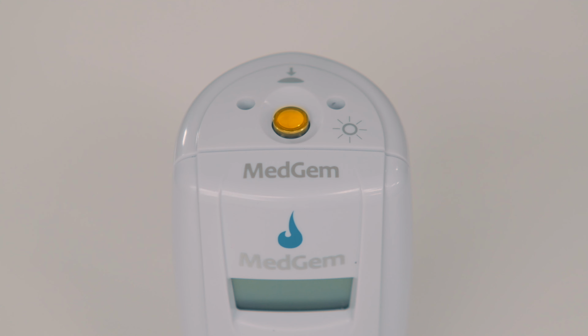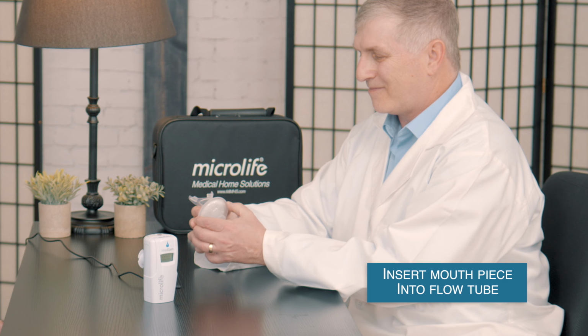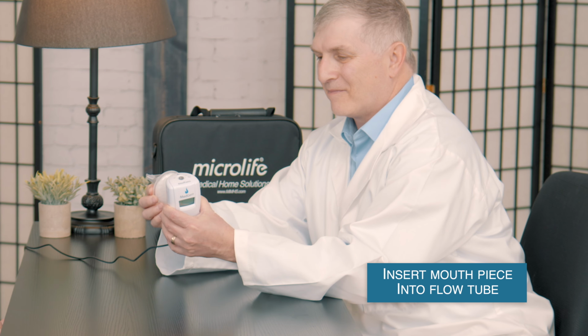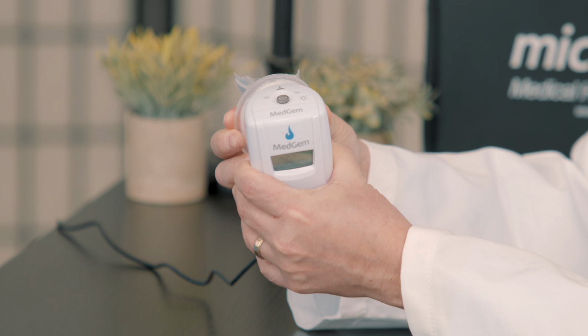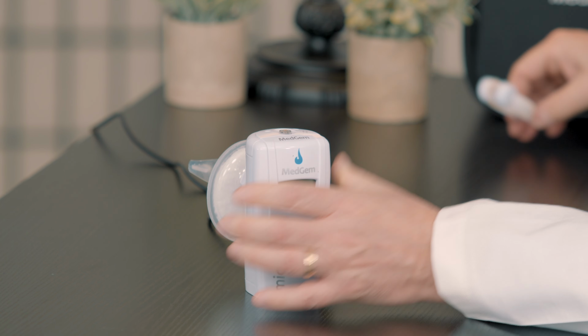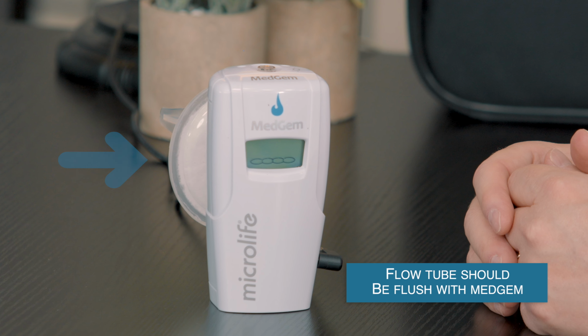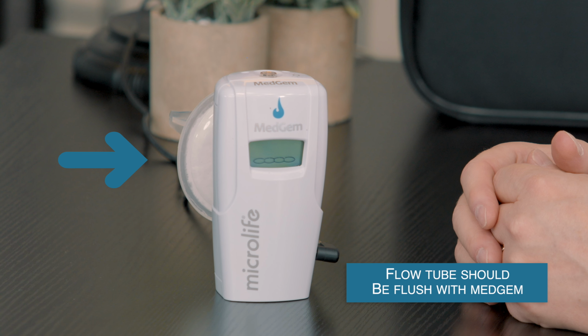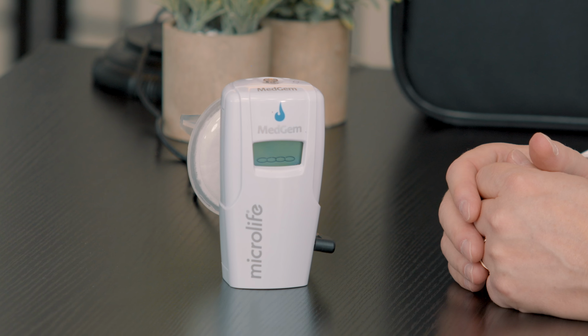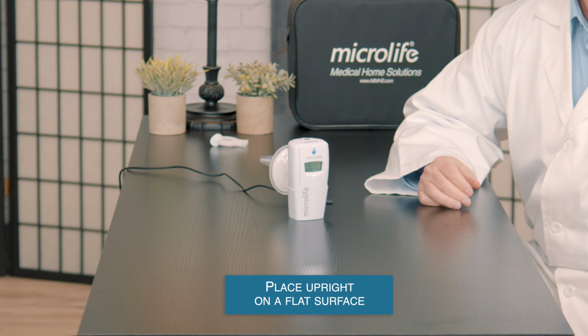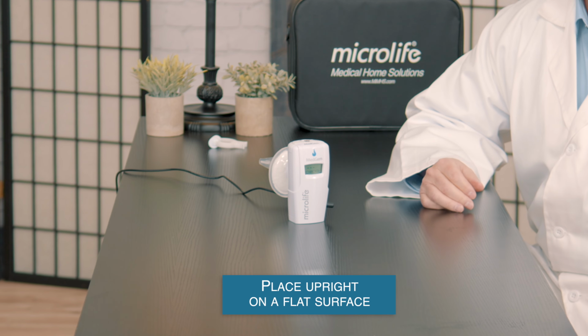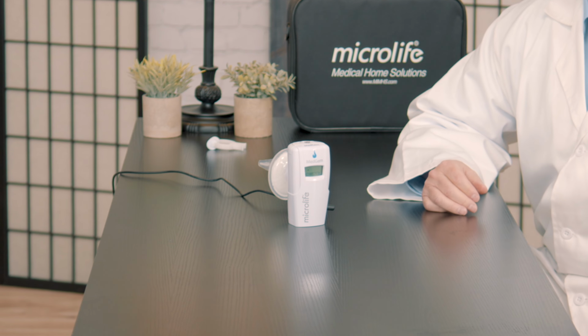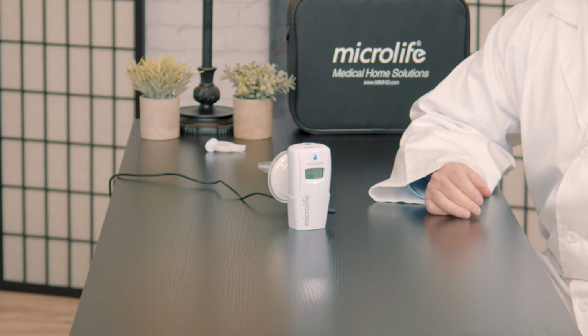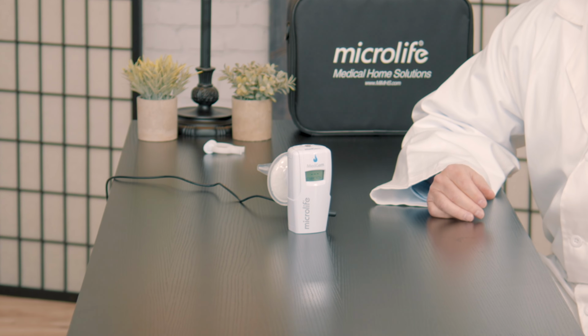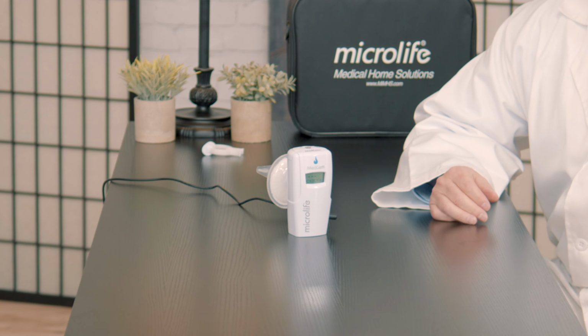Insert the single-use mouthpiece into the flow tube on the back of the device. Ensure they fit snugly to prevent any air leakage. The top of the flow tube should be flush with the MedGem device. This is essential for the accuracy of the measurement. Place the MedGem device upright on a flat surface, away from air vents or fans. It is very important to leave the MedGem device sitting upright on a flat surface throughout the self-calibration period.